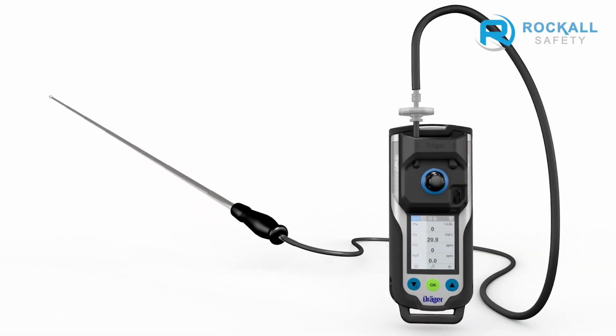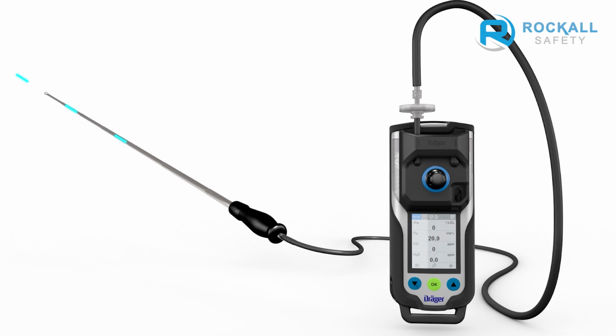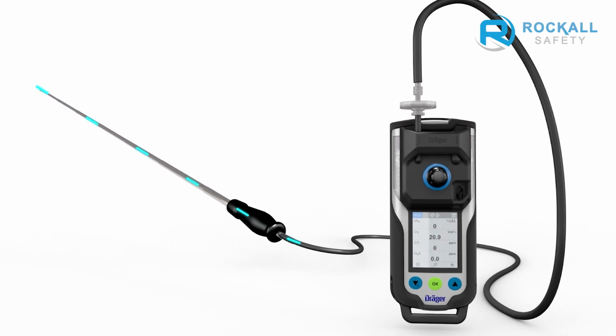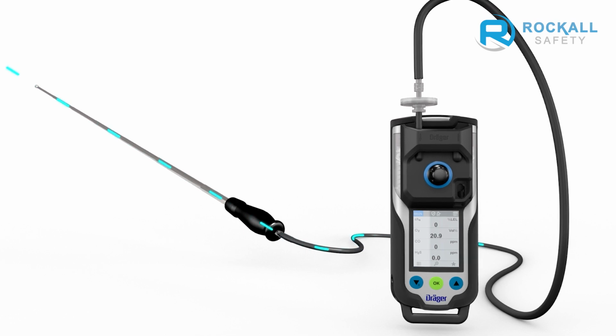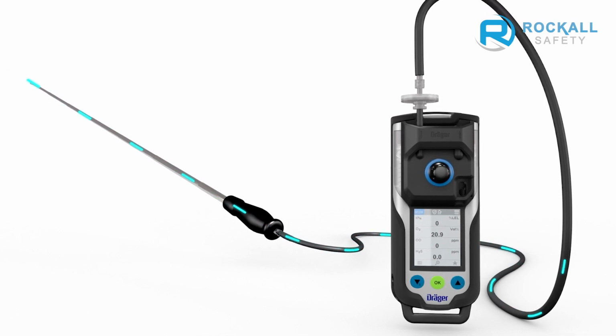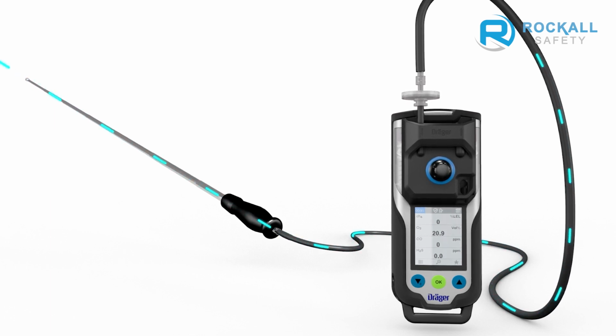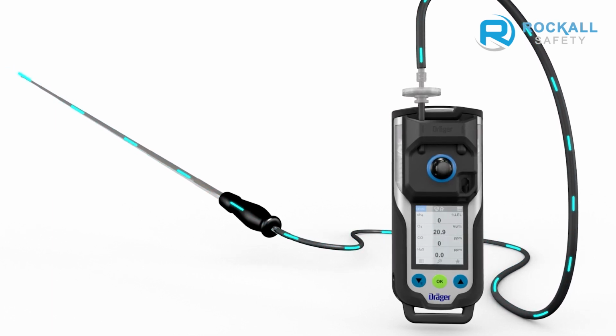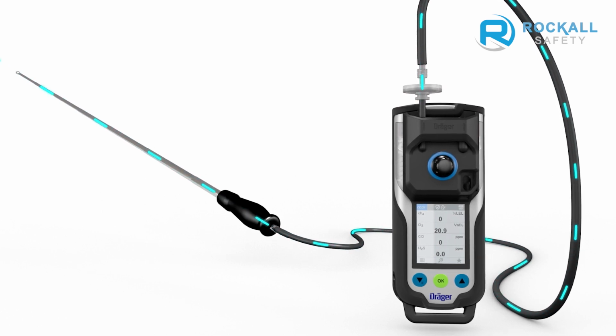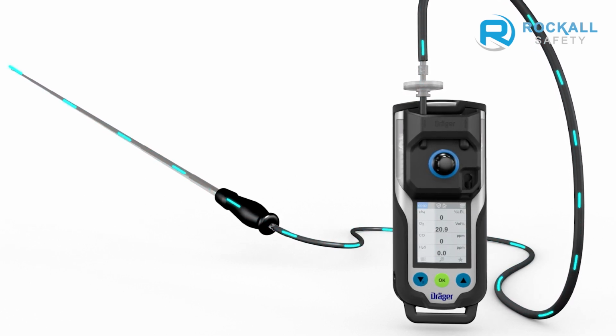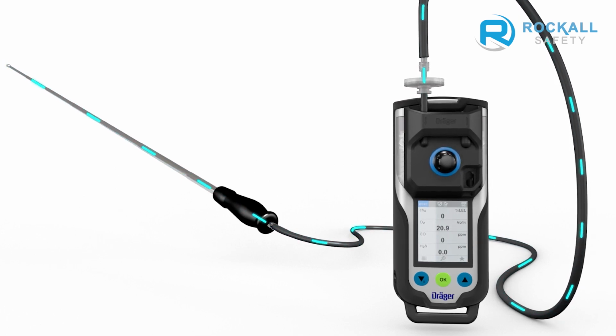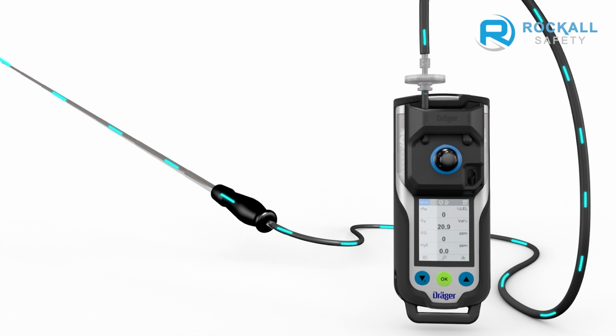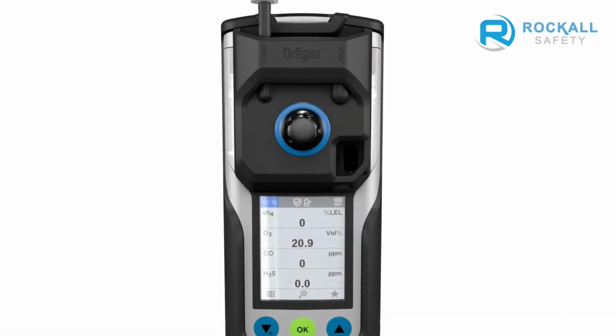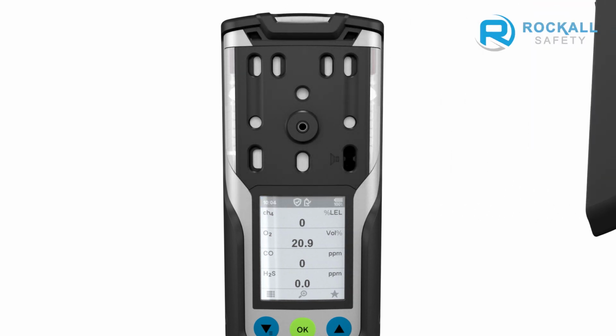Before every measurement, flush the sampling hose or probe with the target gas. Flooding is required to reduce negative influences, such as the gas transport time, for example. As a rule of thumb, a time of 3 seconds per meter can be assumed for standard gases. Wait until the values on the display appear stable. Special gases may require more time. Please note, after flooding with aggressive gases, purge the pump with clean air for several minutes in order to extend the pump life. To end the pump measurement, loosen the pump adapter screw and pull off the adapter. The instrument will automatically switch to diffusion mode.